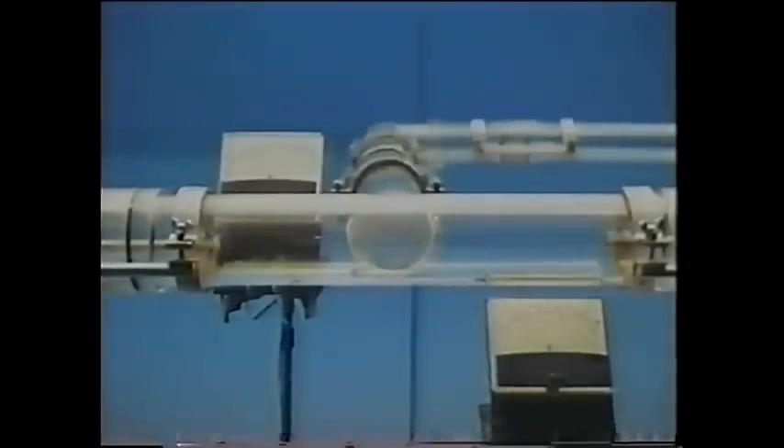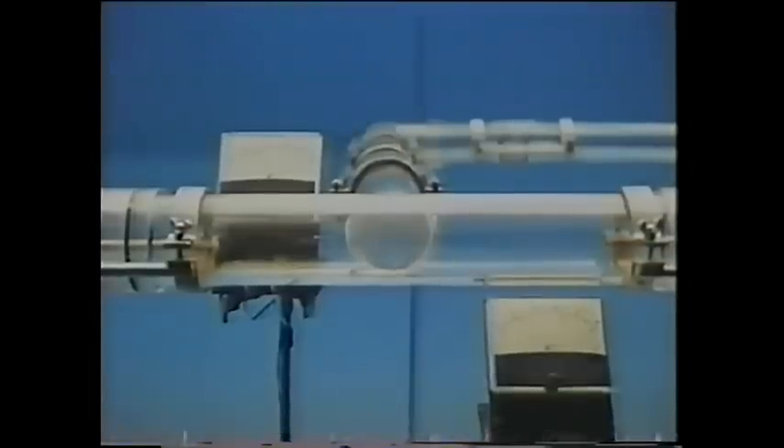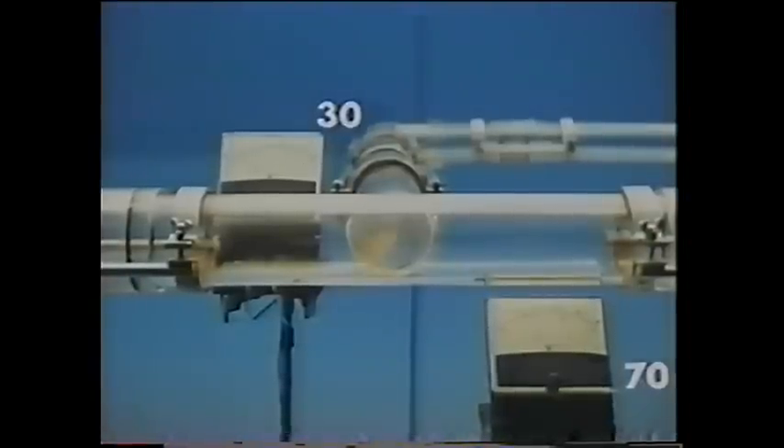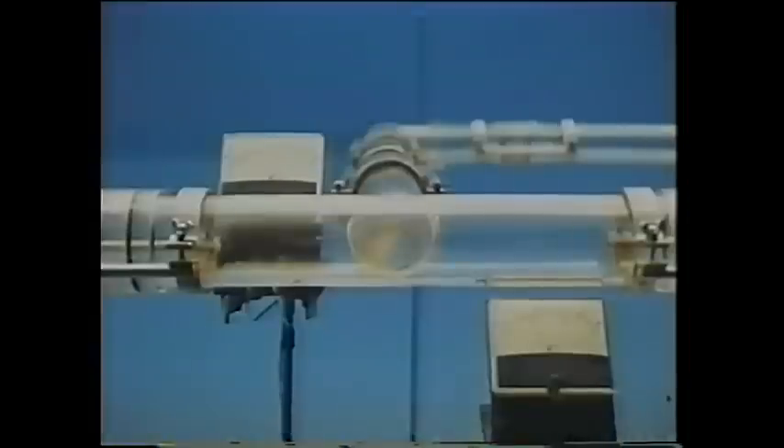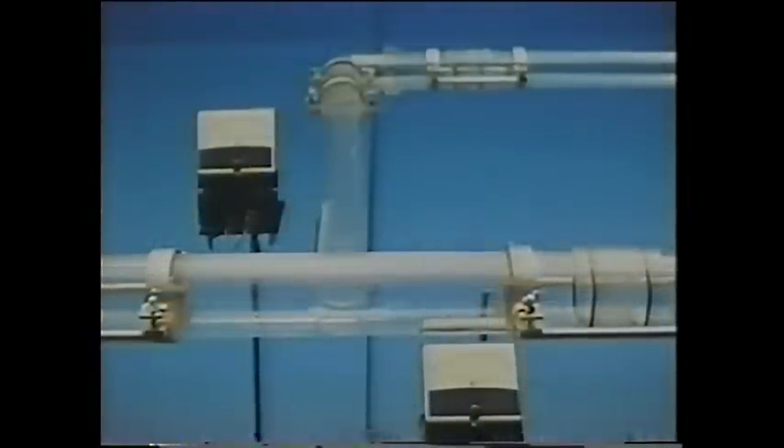This is the model of a pipeline with a branch line. The gas stream comes from the left. The gas flow in the branch line is measured with the meter on the left; the meter on the right measures the gas flow in the straight-through line. At this moment, the gas stream divides into two equal parts. It appears that all of the liquid passes into the branch line. When we lower the gas flow entering the branch line to 30%, all of the liquid still continues to flow into the branch line. It is not until a small part of the gas stream passes into the branch line that liquid flows straight through. In most cases, the liquid flow does not divide at a branch point, but either goes straight on or into the branch. Hence, the liquid flow shows a distinct route preference.